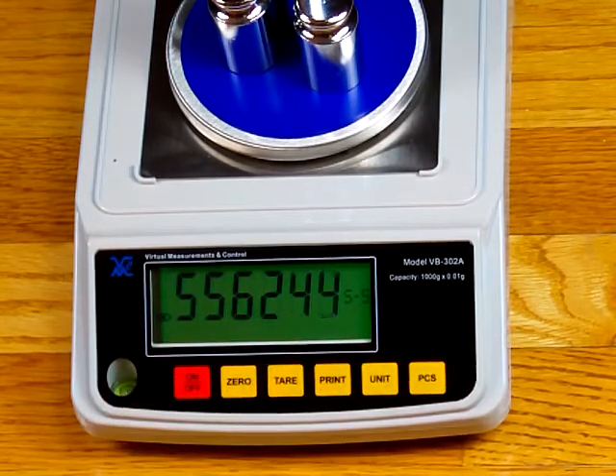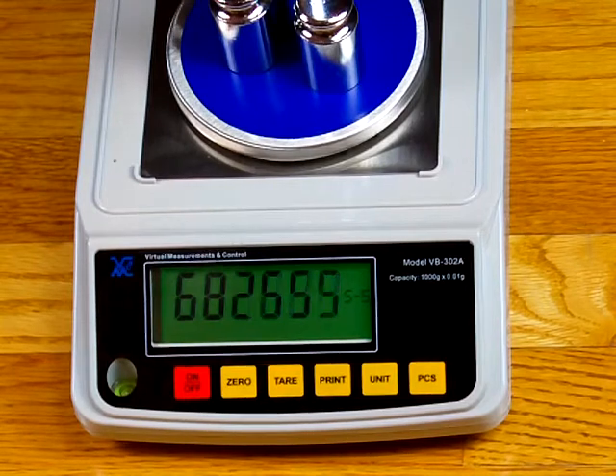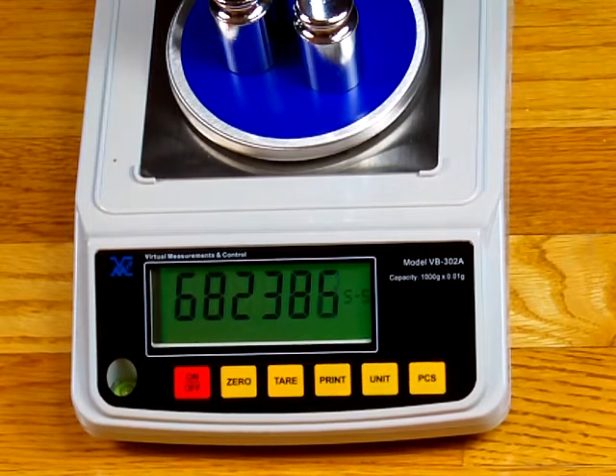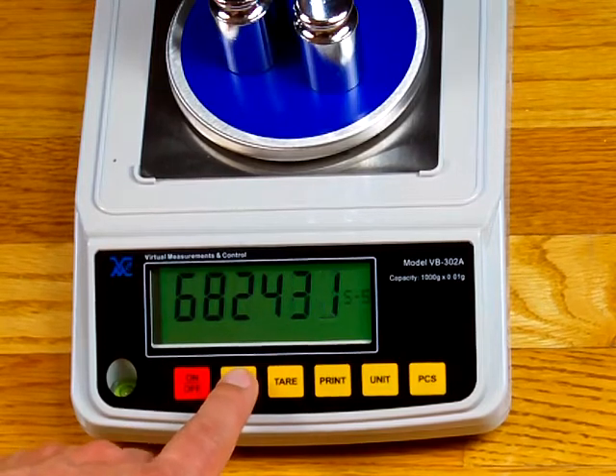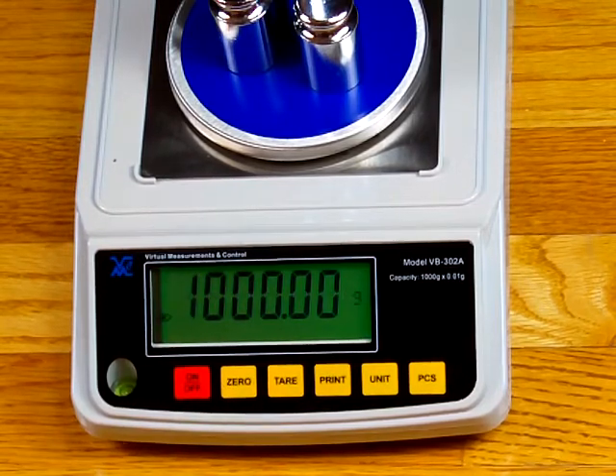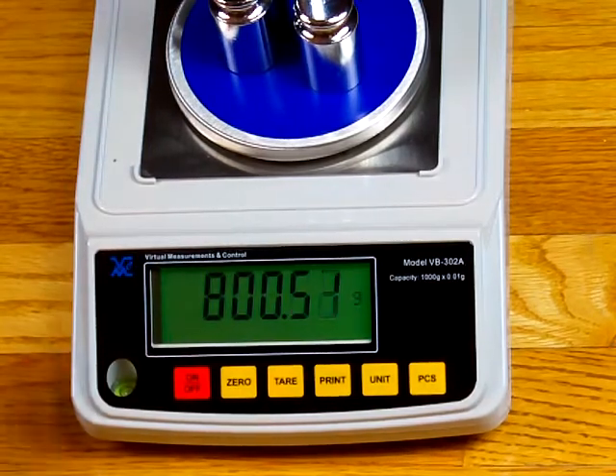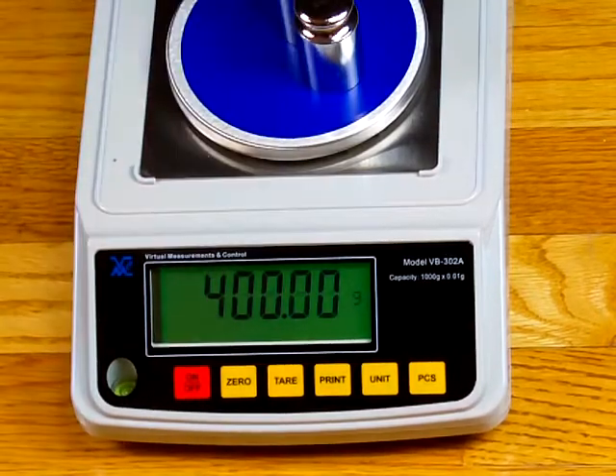And finally, we have S-5, our last 200-gram weight. And the numbers are going to be even more random now because this is a lot of divisions for a strain gauge-based scale. So you'll see some fluctuation. But we'll press the 0 key. And it's stored the last value. So now we have 1,000.